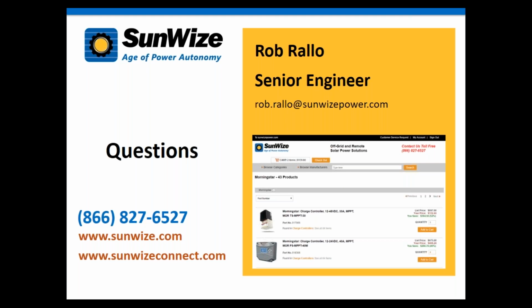All right, thanks. We have one other question, about the concern that having a lot of complex power electronics within the battery box would be an explosion hazard itself. Rob, I'll let you answer this, but I believe a lot of the specifications and requirements we went over are for non-hazardous locations. If you place the electronics within an enclosure in a truly hazardous location rated zone, depending on the exact hazard rating, you may need to certify either all the components or the whole system to something like Class 1 Division 2.